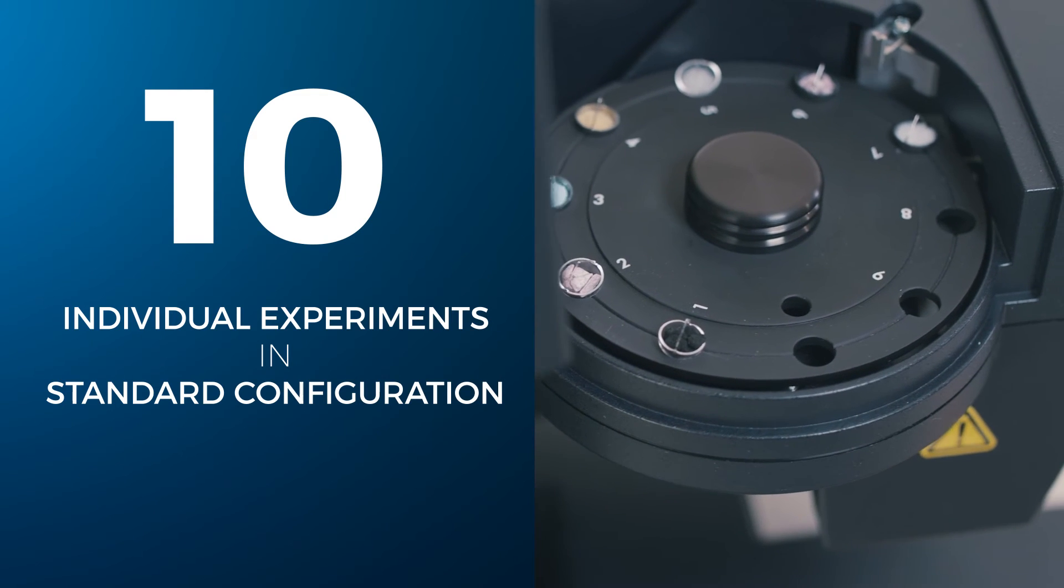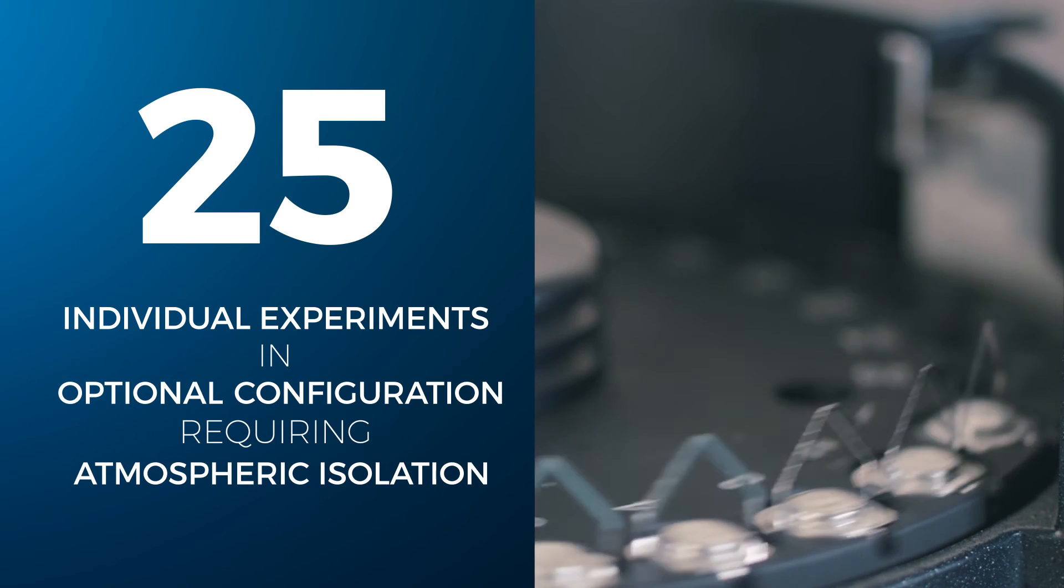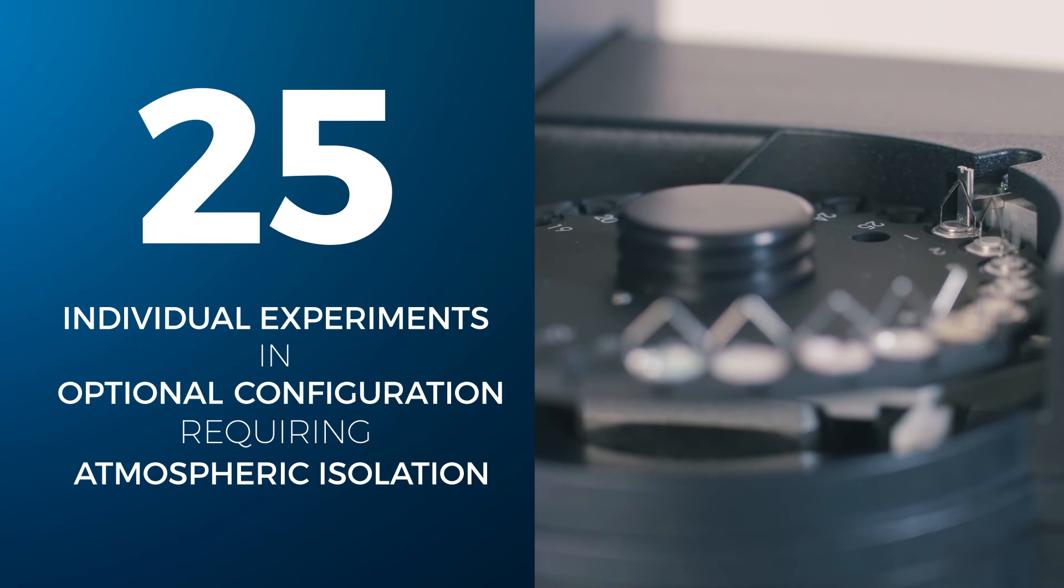The Discovery SA Auto Sampler programs up to 10 individual experiments in its standard configuration. It can be upgraded to a 25 position tray for samples requiring atmospheric isolation, with the availability to punch open the pan just prior to analysis.